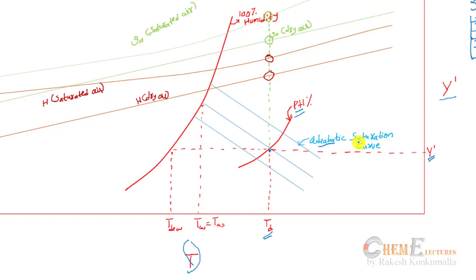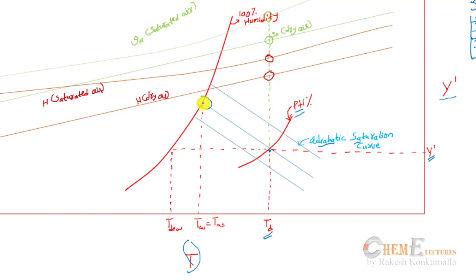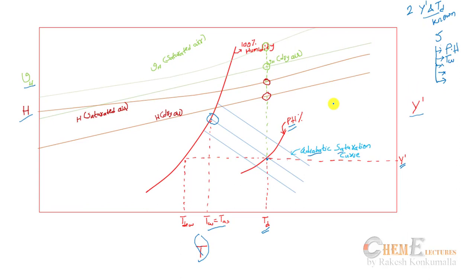These are the adiabatic saturation curve lines. As you have the point of intersection of T_d and Y', simply follow the adiabatic saturation curve until the 100% humidity — completely saturated. At complete saturation you get the adiabatic saturation temperature. For an air-water system, the adiabatic saturation temperature and wet bulb temperature are equal, so on the x-axis you get the wet bulb temperature.